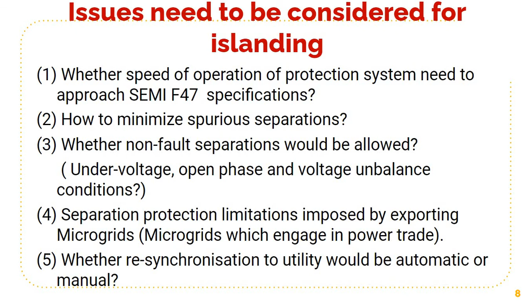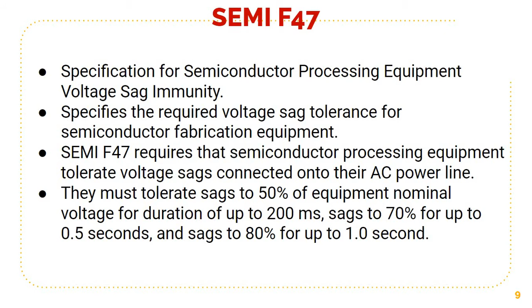So let us see what is SEMI F47. It is a specification for semiconductor processing equipment voltage sag immunity. SEMI F47 specifies the required voltage sag tolerance for semiconductor fabrication equipment. So it requires that semiconductor processing equipment tolerate voltage sags on their power line, typically AC power line. So they must tolerate sags to 50% of equipment nominal voltage for a duration of 200 milliseconds, sags of magnitude 70% for up to 0.5 seconds, and sags to 80% for up to 1 second.